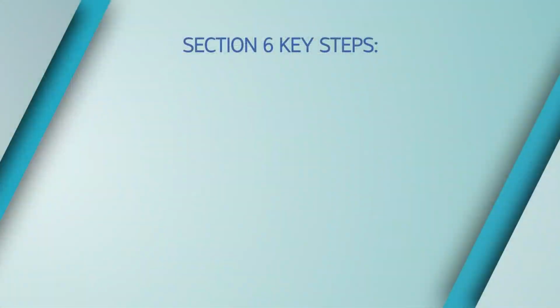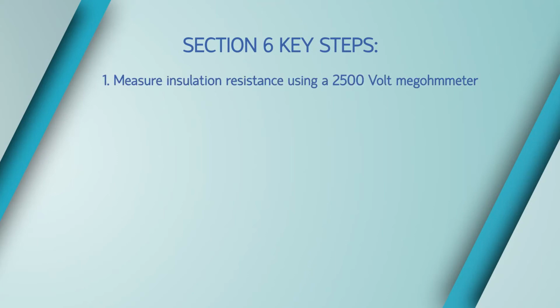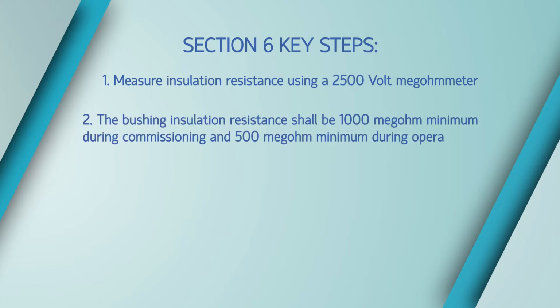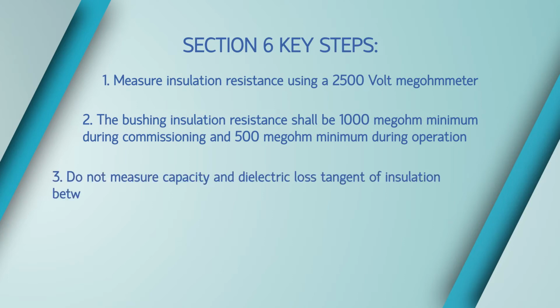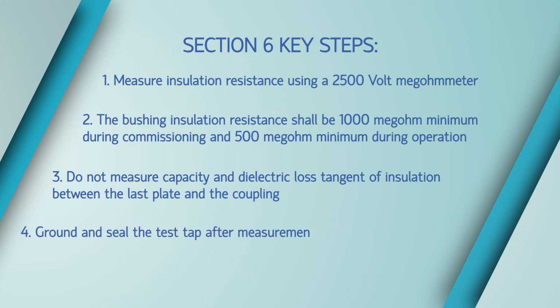Let us go through the key steps again. Measure insulation resistance using a 2500 volt megohm meter. The bushing insulation resistance shall be 1000 megohm minimum during commissioning and 500 megohm minimum during operation. Do not measure capacity and dielectric loss tangent of insulation between the last plate and the coupling. Ground and seal the test tap after measurements.